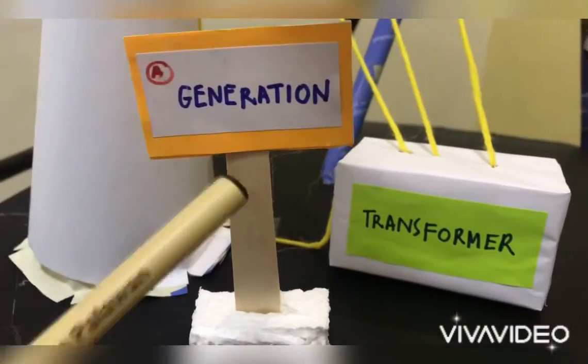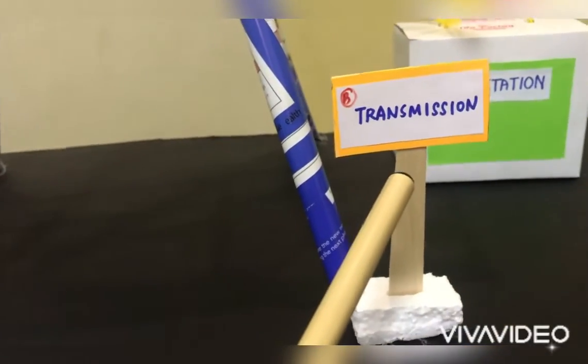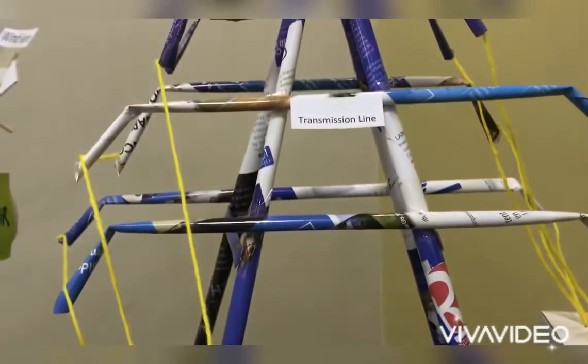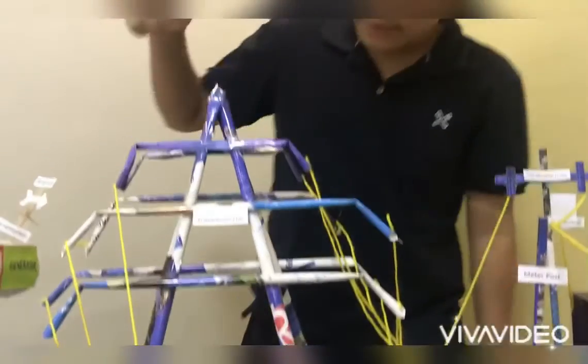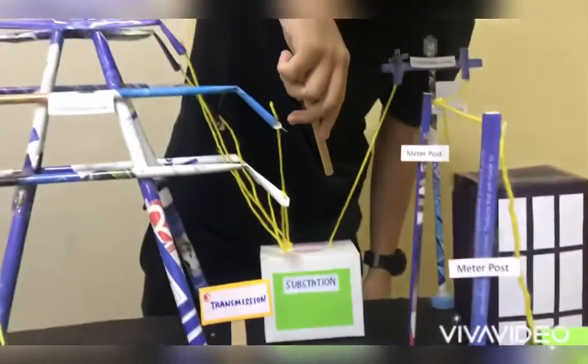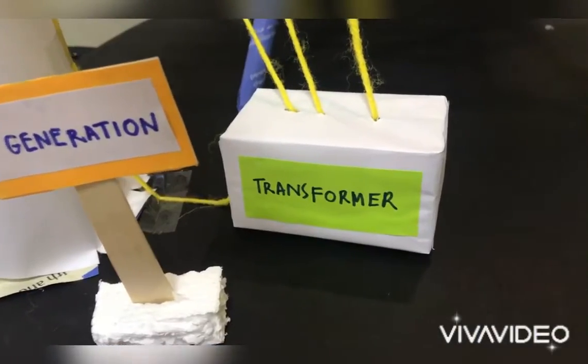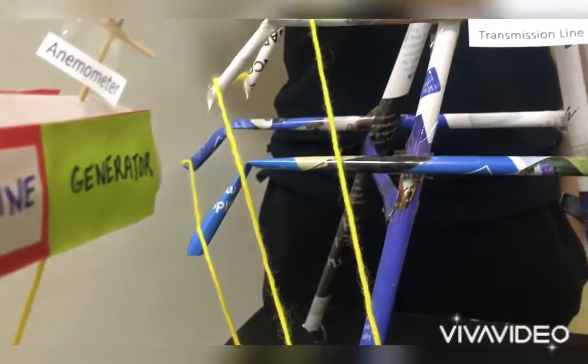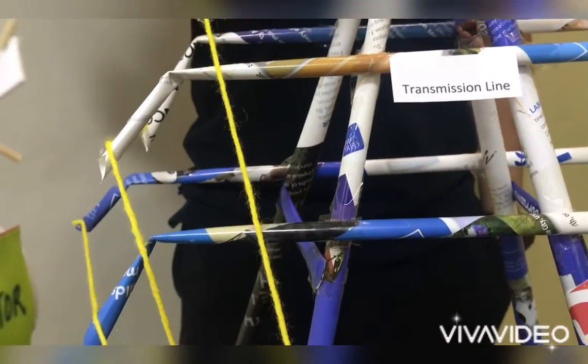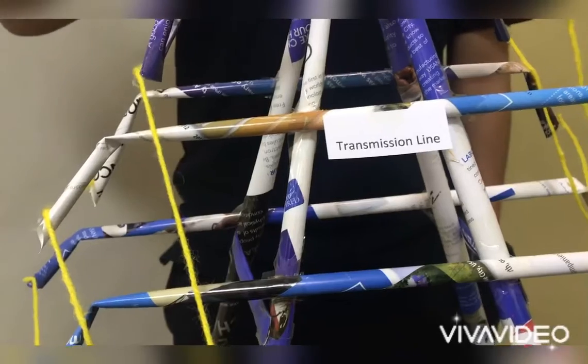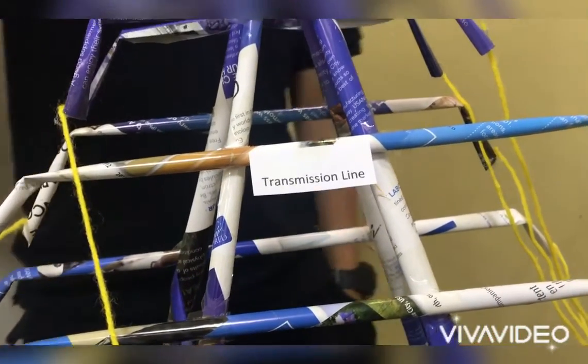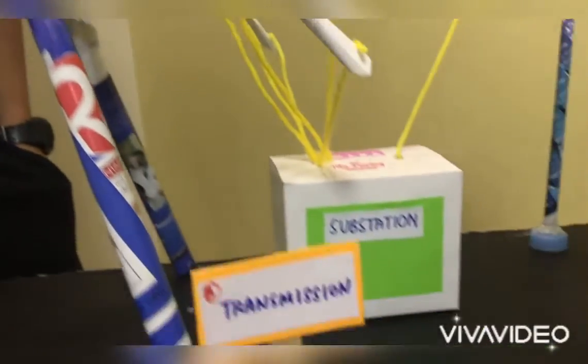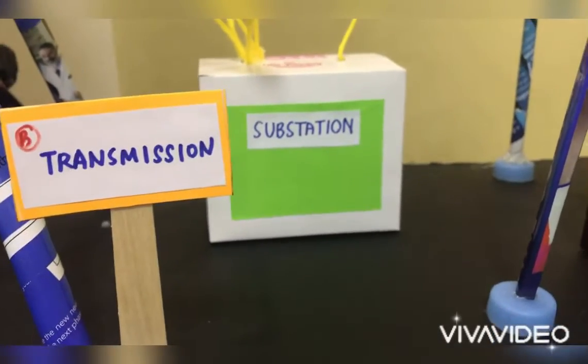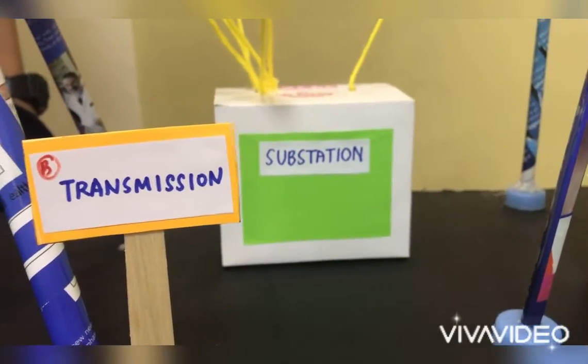This is the generation. The second process is called electric transmission, which is the vital link between power production and power usage. We have here the transmission line and the substation. The transformer can raise the voltage produced by a wind turbine generator from, for example, 2,200 volts into 220,000 volts. The high voltage electricity is then transmitted through the transmission line to substations. A substation is a set of equipment reducing the high voltage of electrical power transmission to a level suitable for supply to consumers.